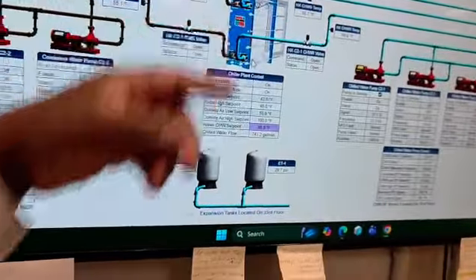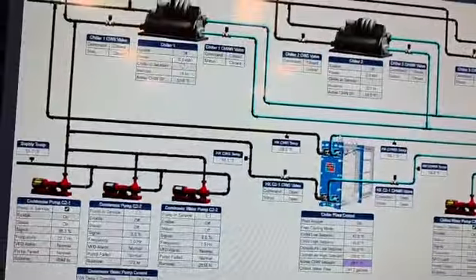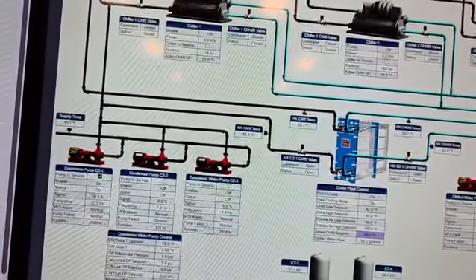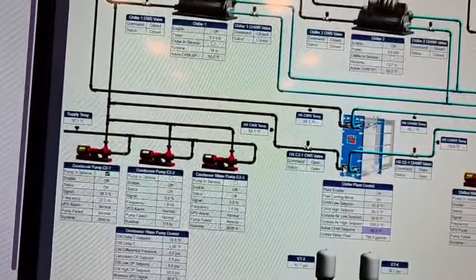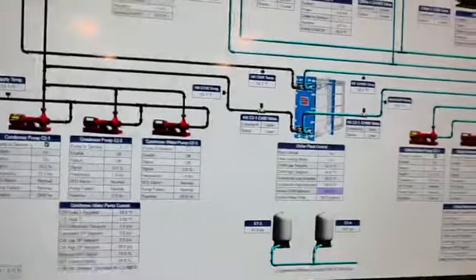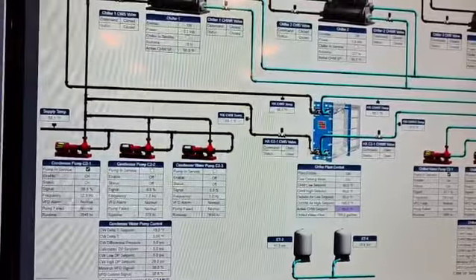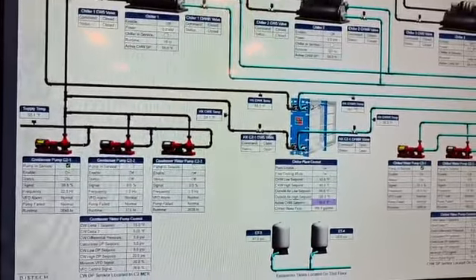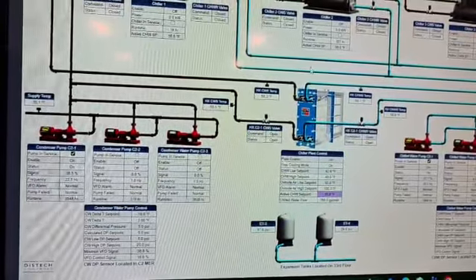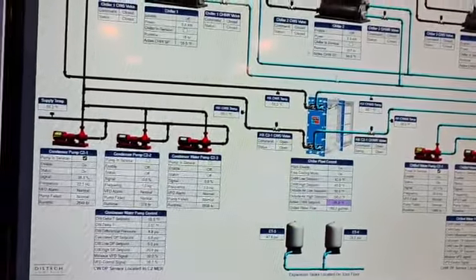I see. So over here, it comes in from the bottom and goes out through the top too? I'm not sure. I think so. Usually they want to feed from the bottom because you want to push the air out. Right, because hot air rises. If you feed from the top, sometimes there could be an air trap. So most of the time they feed from the bottom to push the air out, and then you have relief valves in the system. I see. It's just air inside of the loop.